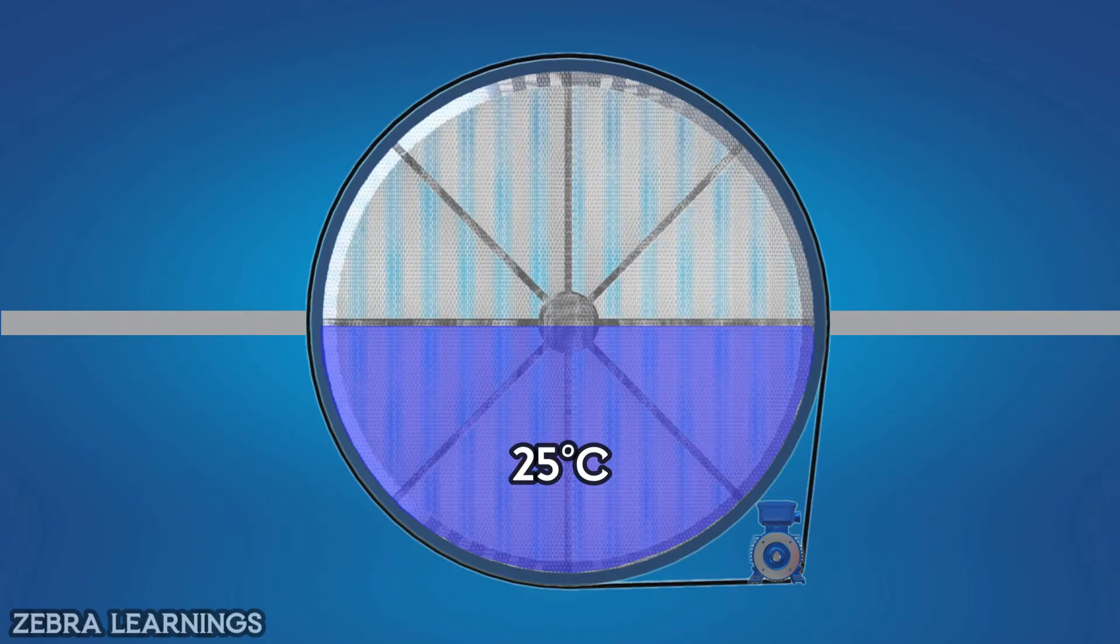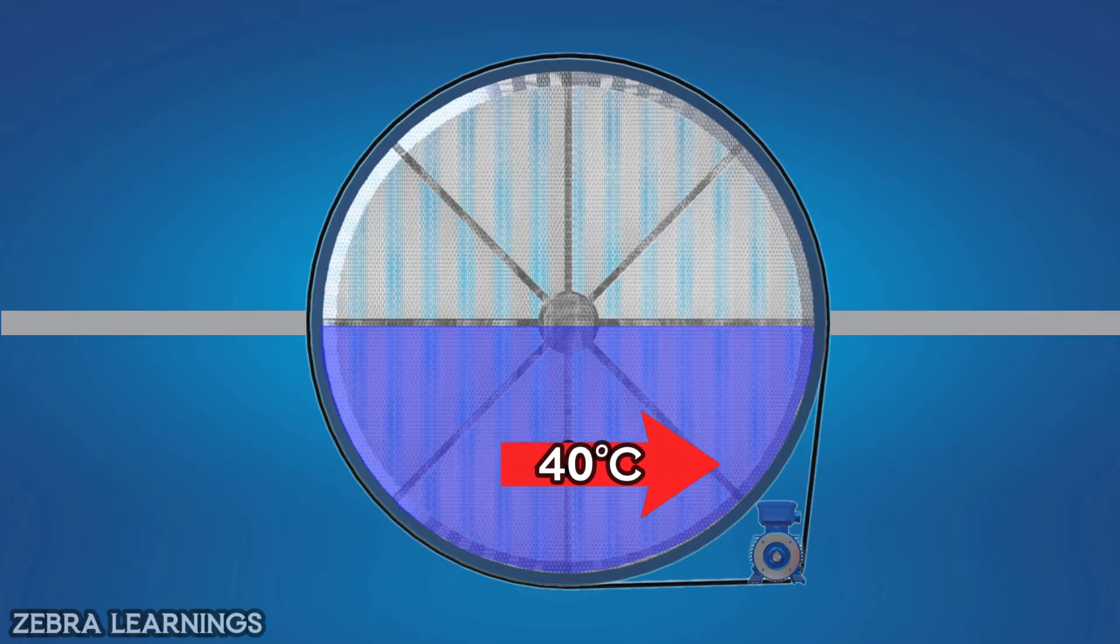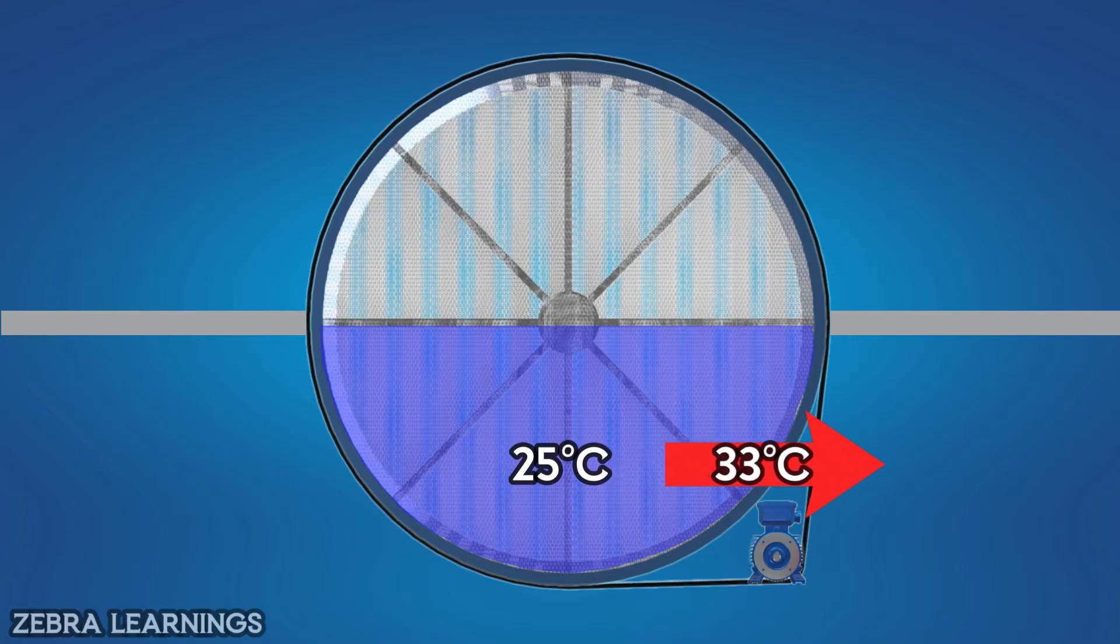The outside air comes in at 40 degrees Celsius in the lower part. Air at a temperature of 40 degrees Celsius travels through a thermal wheel at a temperature of 25 degrees Celsius, and the air temperature drops to exit the thermal wheel at 33 degrees Celsius.